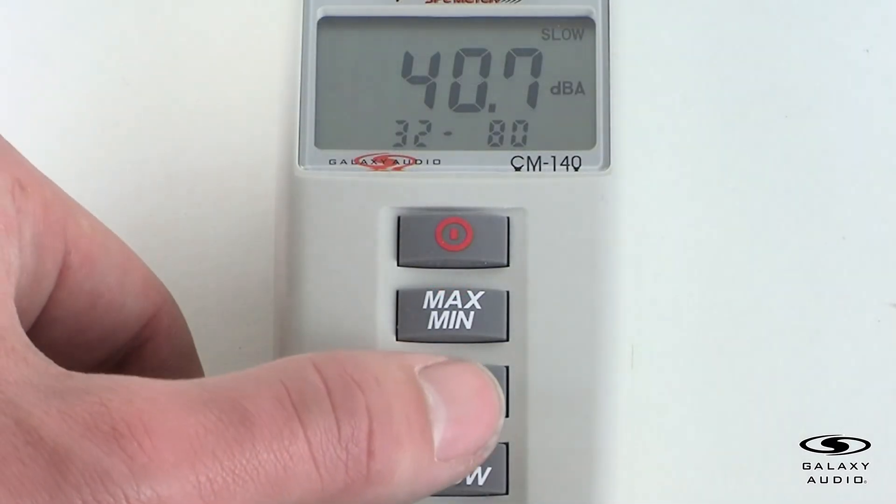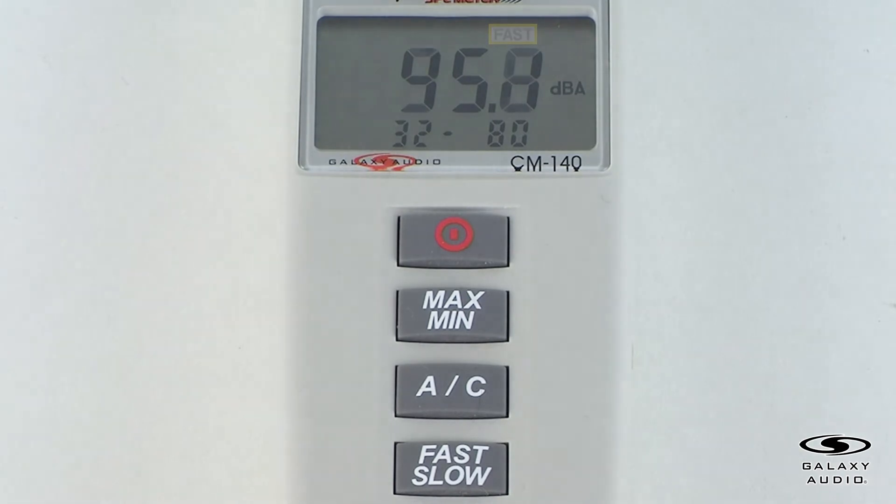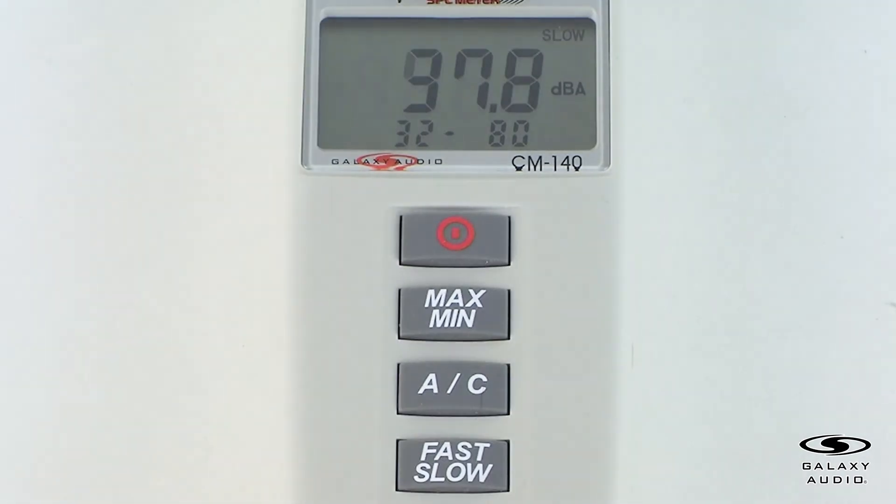For the time weighting select button, the fast setting is for normal measurements and gives better indication of peaks. The slow setting is for checking average levels of fluctuating noise.